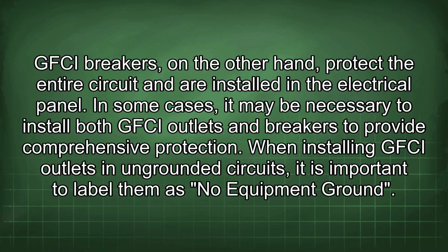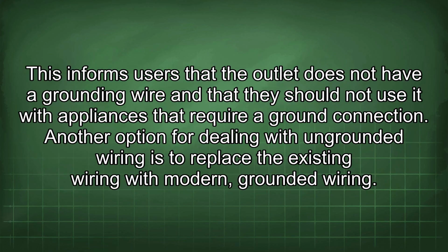When installing GFCI outlets in ungrounded circuits, it is important to label them as "no equipment ground." This informs users that the outlet does not have a grounding wire and that they should not use it with appliances that require a ground connection.